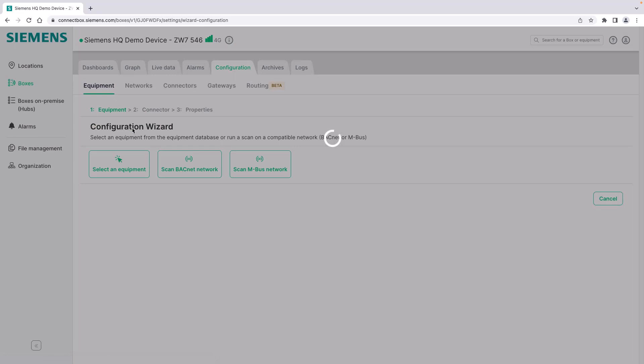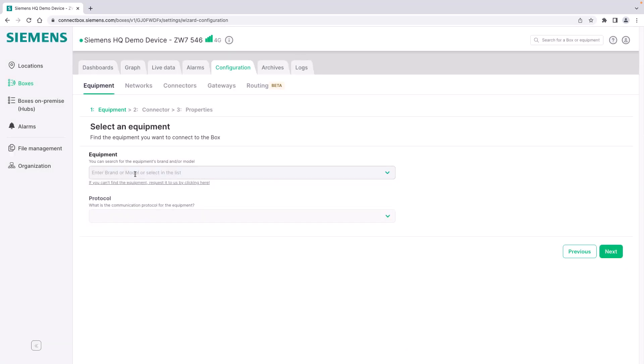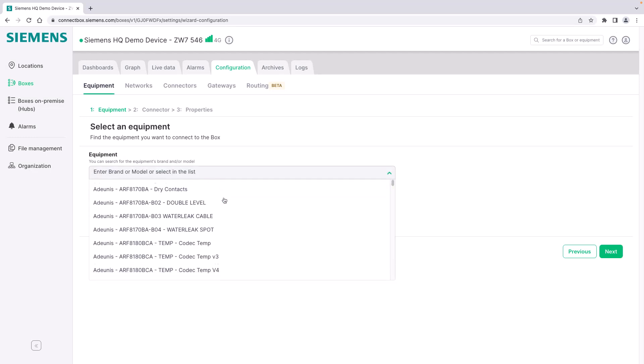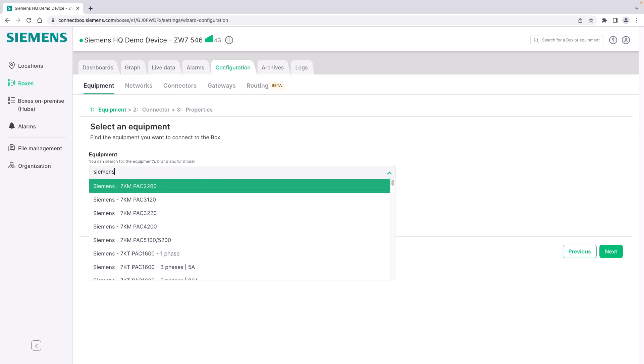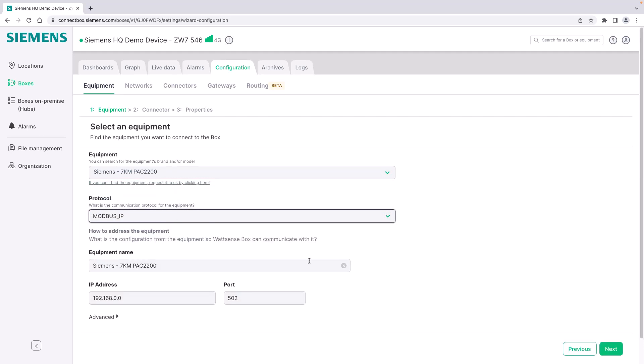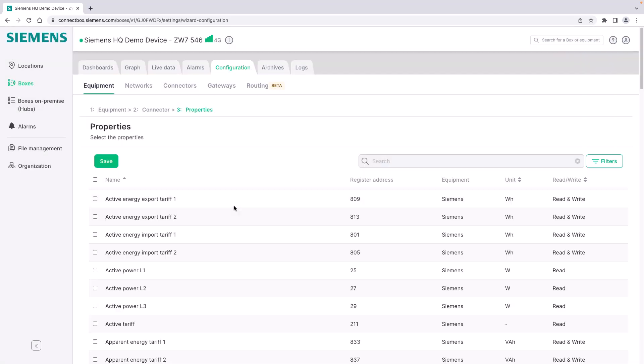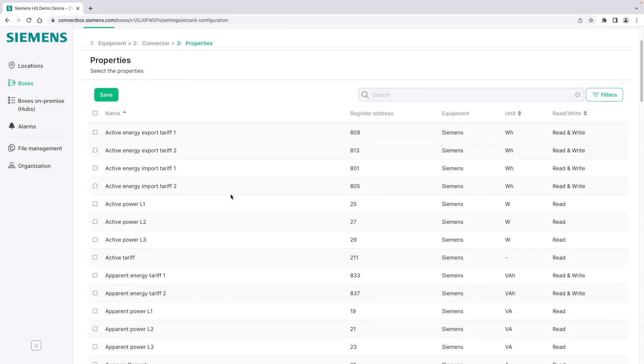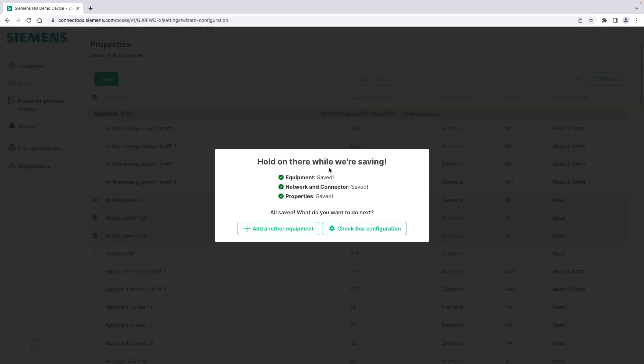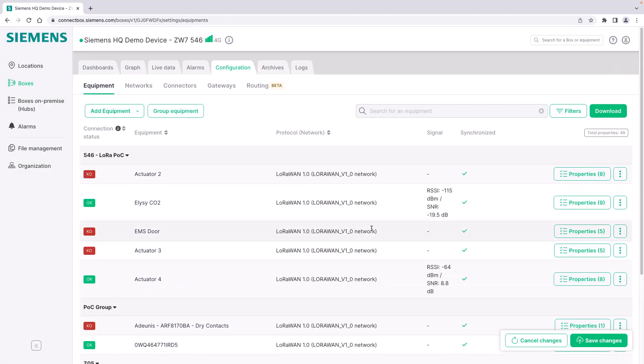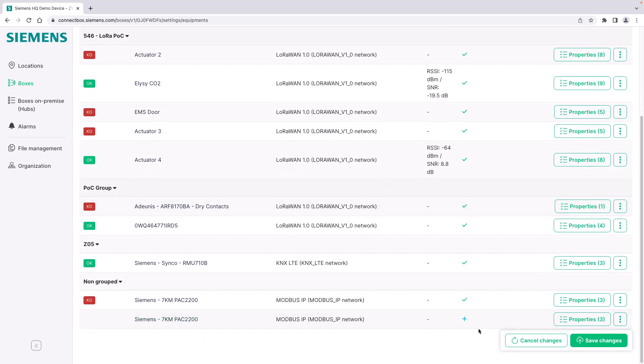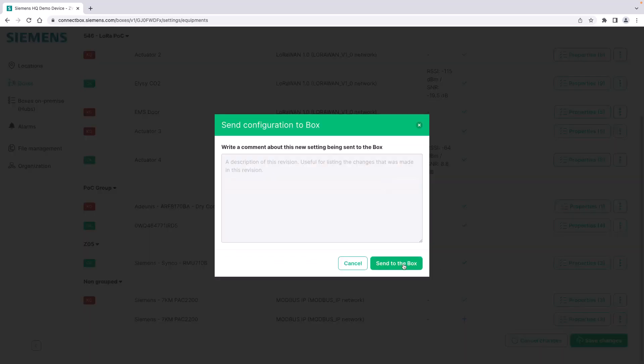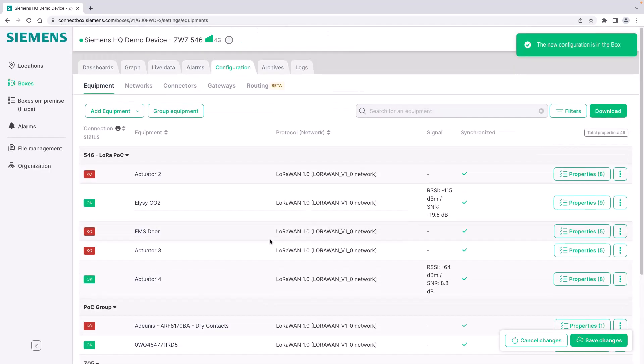Going back, I will show you the third functionality and this is selecting the equipment from the equipment catalog. This is definitely the easiest way because we have a long list of manufacturers and devices already prepared for you. For example, the Siemens Sentron PAC electricity meters - you simply select them, we already suggest the protocol, in this case we go with Modbus IP. I already configured the IP address and the port, I can change it here, click on next and it already shows me all the data points that I can integrate, for example the power of the three phases. I click on save and the equipment is automatically added to my network and the connect box.